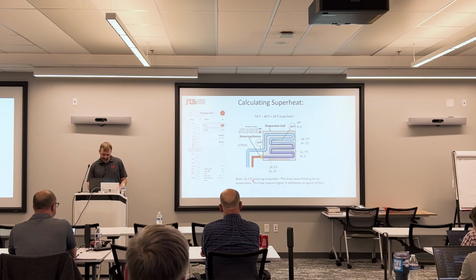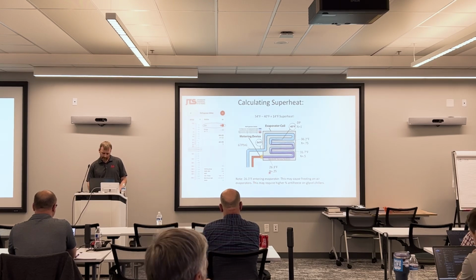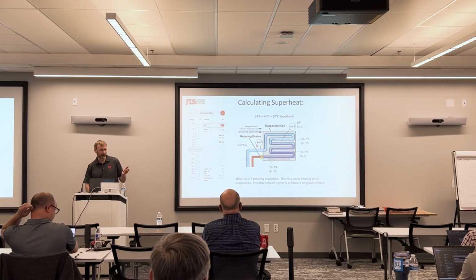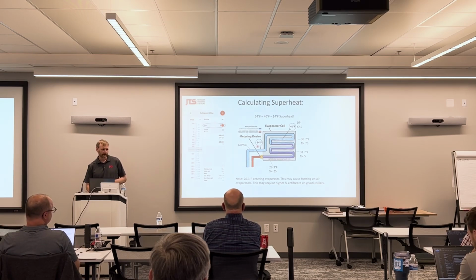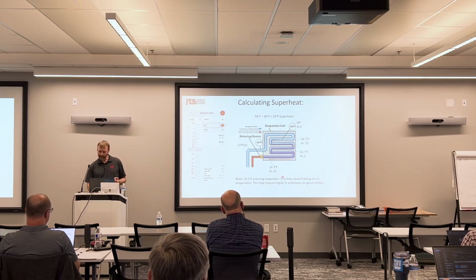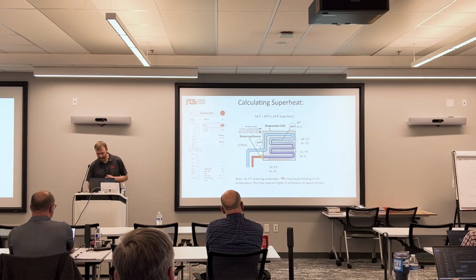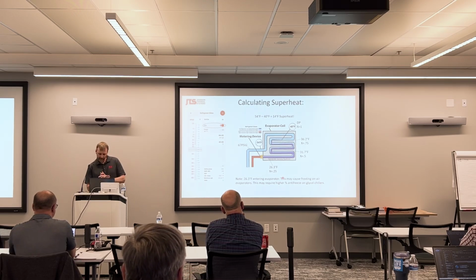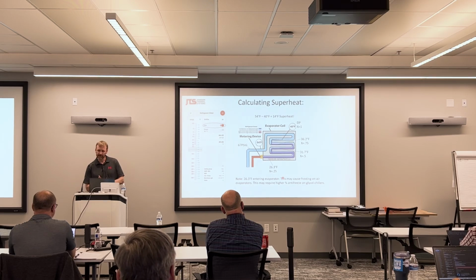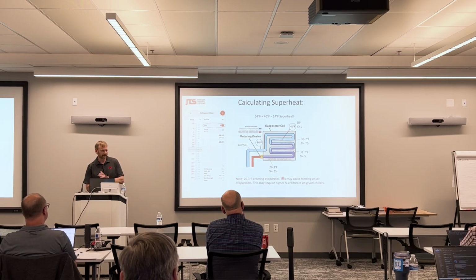One thing that's interesting to note, 26 degrees on an evaporator coil is pretty cold, especially if maybe this is a 60 degree air temperature application. It's possible that the amount of glide may cause frosting to happen on air heat exchangers at an earlier, warmer temperature. It's also possible in liquid chiller applications that you may need more antifreeze to protect against freezing.